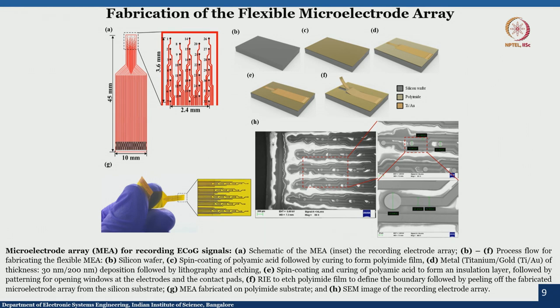To improve the resolution, we started fabricating a 32-channel high-density microelectrode array. For the rat's brain, 32 channels is considered a high density. The material used as substrate is polyimide, coated on a silicon wafer, but the final device is made out of the polyimide substrate. On the polyimide substrate, we have titanium and gold patterned, then polyimide is spun again as an insulating material, and photolithography is performed to expose the recording electrodes and contact electrodes.